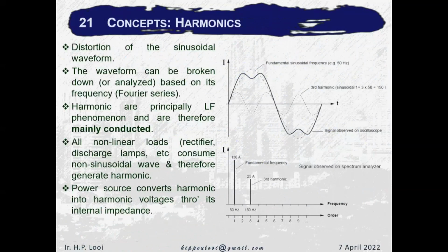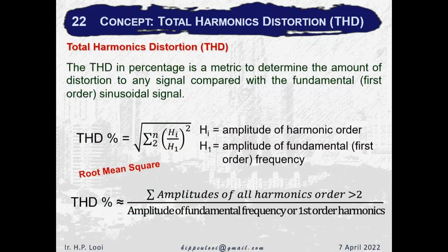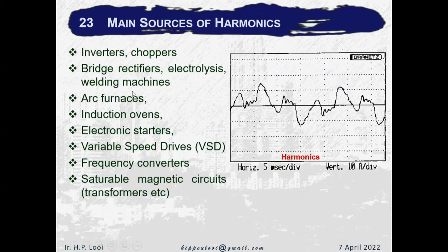So harmonics is a distortion of the waveform. And if you remember your basic electrical theory, any waveform can actually be summed up as a Fourier series of signals. So total harmonic distortion is a metric to determine how much distortion there is in a fundamental, which in Malaysia is 50 hertz. In other countries it might be 60. The main source of harmonics is non-linear loads.